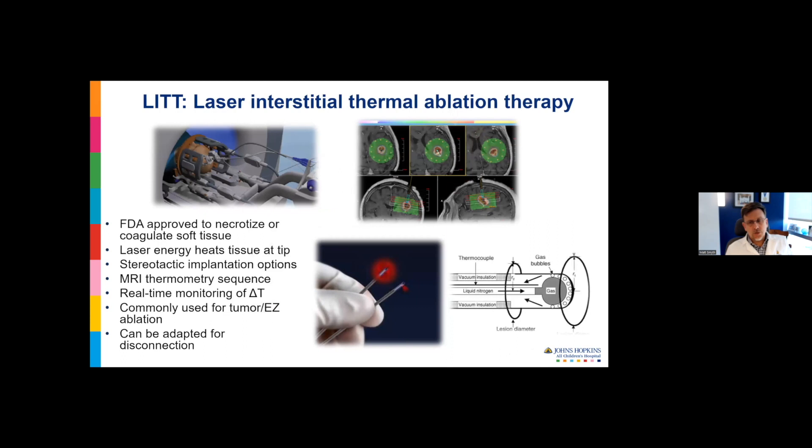So laser ablation—what is this? In the United States, our FDA has approved this system to necrotize or coagulate soft tissue in the body as well as in the brain. The MRI compatible laser fiber is introduced into the target, and then the laser is activated and the energy is translated from light into heat. The key is that the MRI scan is done in real time using a thermometry phase sequence, and it calculates a delta T or change in temperature from baseline and generates a thermal damage estimate of the region of ablation.